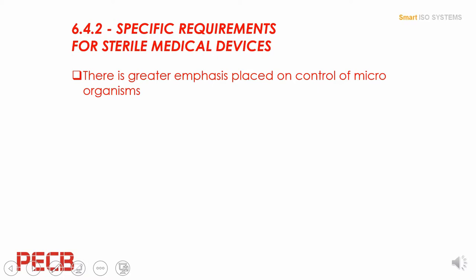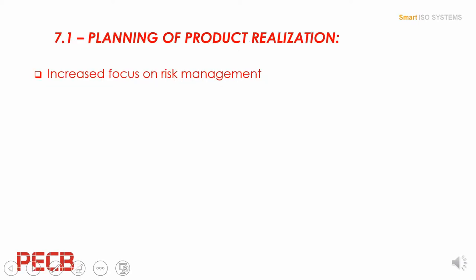There is now a subclause on sterile medical devices. The standard requires that you take additional measures for these types of products, where there is a need to prevent contamination with particulate matter or microorganisms and maintain a level of cleanliness during the assembly and packaging operations. Here again, there is an increased focus on risk management.